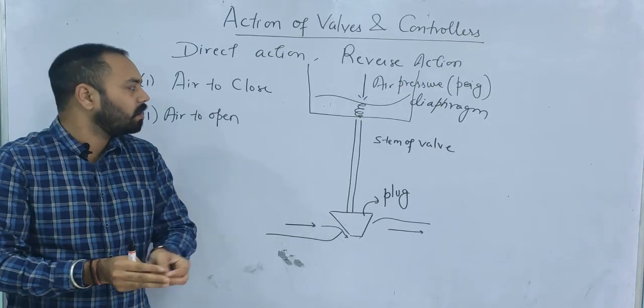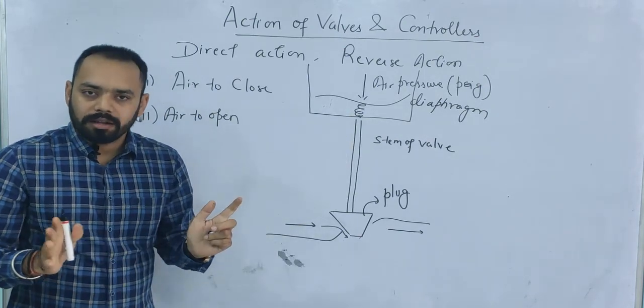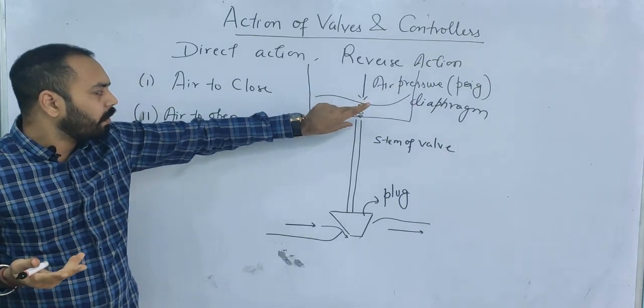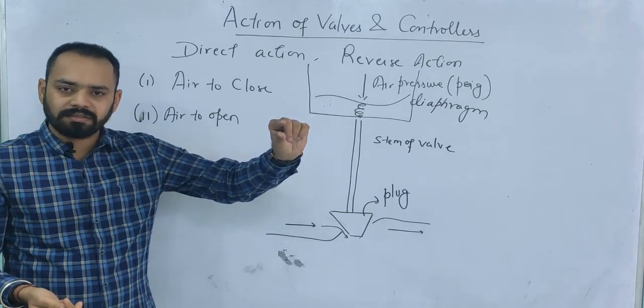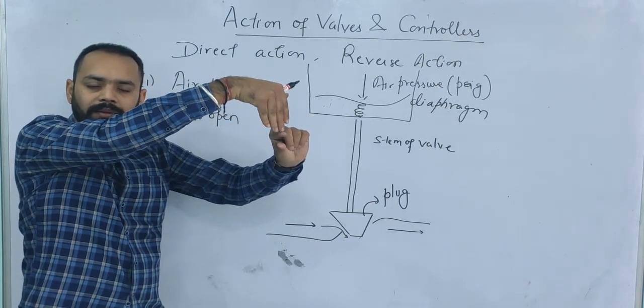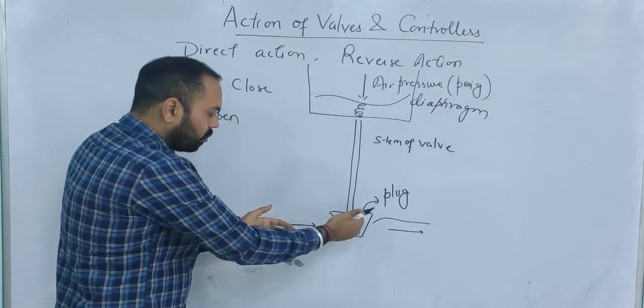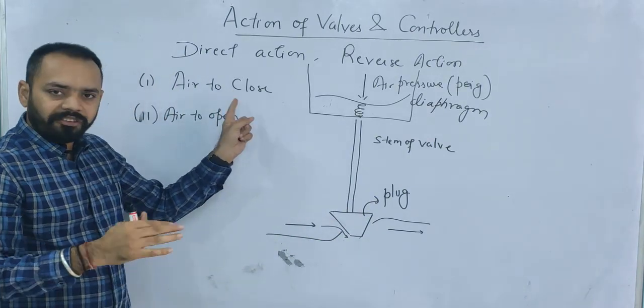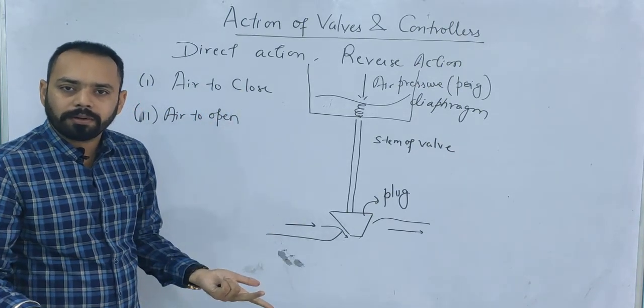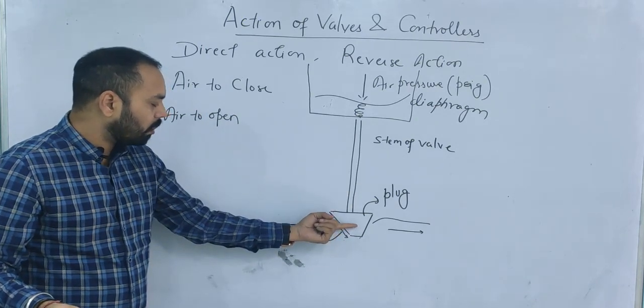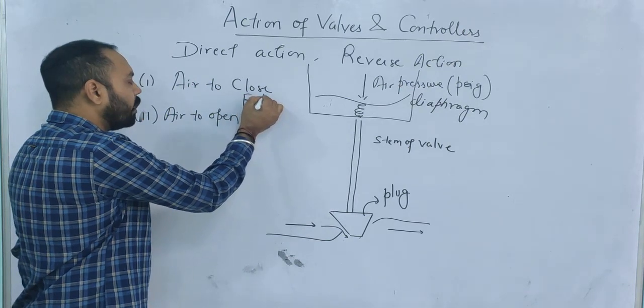Now think: suppose the controller fails and is not able to send a signal to the valve — no air signal, no psig signal. This condition is called the failure condition. What happens? The spring, which was compressed before, restores to its original position — it is the tendency of a spring. When the signal is lost, the spring regains its original position, the stem shifts upwards, and the flow area is completely open. This is why the air-to-close valve is also called a fail-open valve.